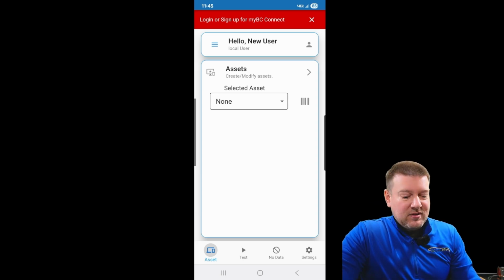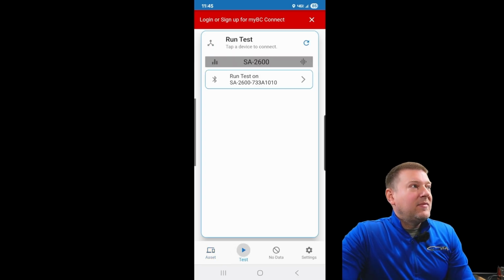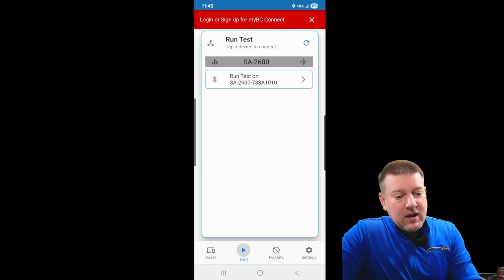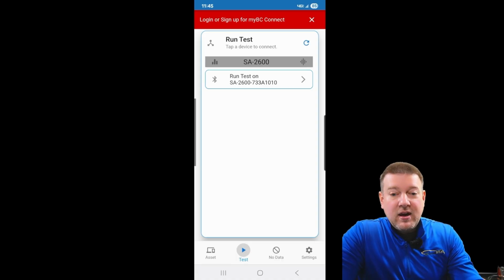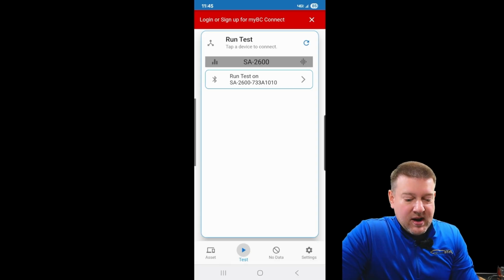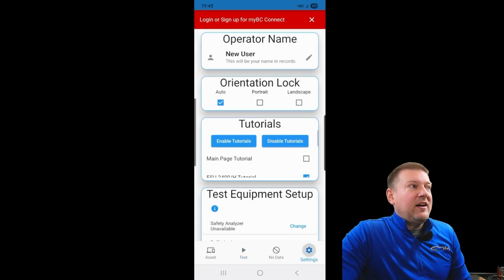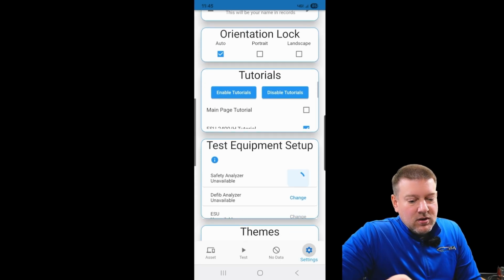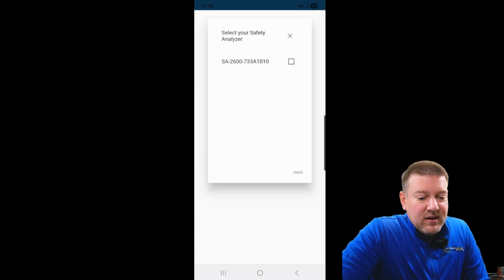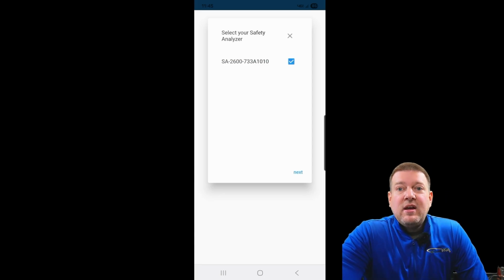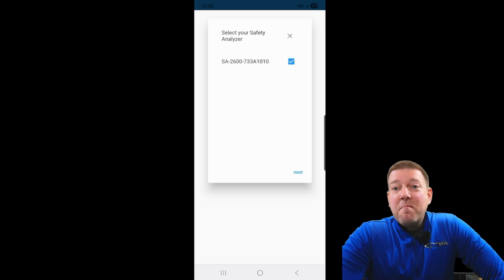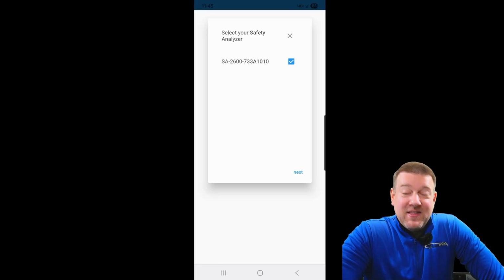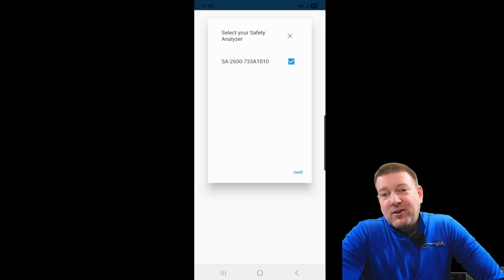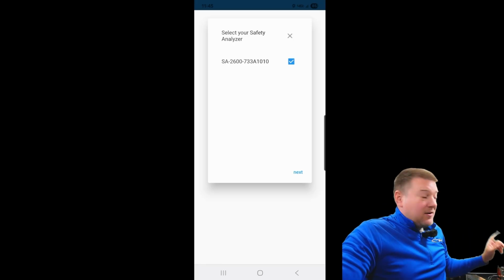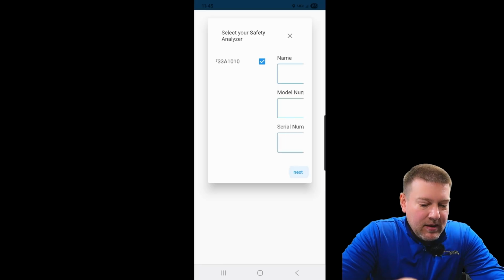You do have one option, and that is to come in and we can do test. So you can see right here, it is actually saying that I have a Bluetooth connected SA-2600. See it right there. However, I'm going to show you guys how you can easily go in and select a safety analyzer right down here. You can make sure the device is powered up now. And here you can select what safety analyzer you're going to be using. This is going to be pretty important because if you work in a biomed shop where you have a multitude of safety analyzers running at the same time, you don't want to be pulling somebody else's results. That could be absolutely catastrophic. So make sure you have the correct one. You can see that we have a code right there. It's going to correspond to the device that I have over here on the table. I'm going to click next.